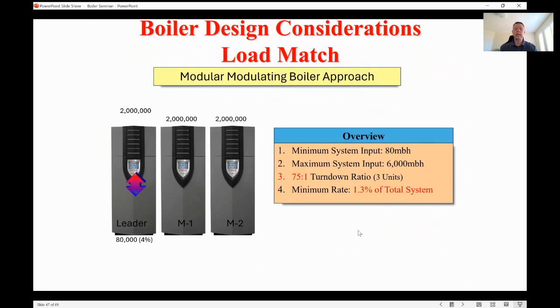So that means we're modulating this plant from the lowest rate on this boiler would be 80 MBH, all the way up to, all of them together at 6 million. So basically, you'd be matching that load from 1.3% of the system load, all the way from that warmest day of the year, all the way to that coldest day of the year. And you're going to be significantly more efficient than, let's say, you put in 3 5-to-1 turn down ratio boilers. Well, that will give you an overall boiler plant turn down ratio of 15-to-1. You'd have significantly more start-stop cycles. You'd be less efficient, and you're going to need maintenance faster. So definitely look at turn down ratio if you have a customer that's concerned about efficiency and is concerned about maintenance.